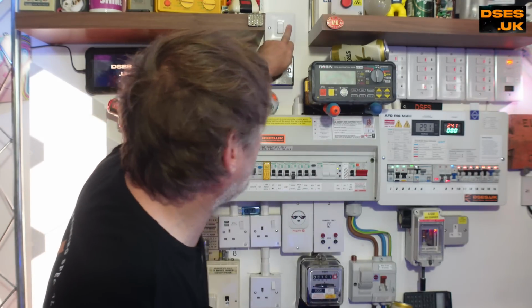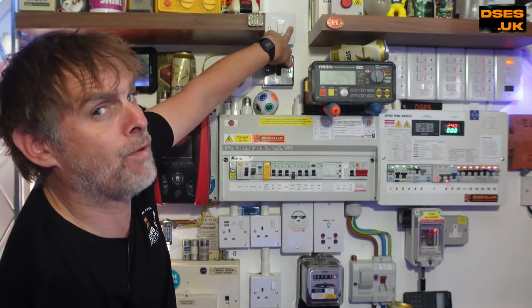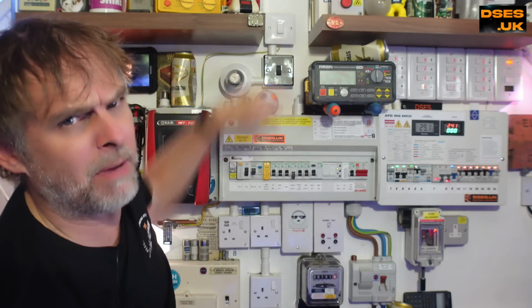In the same way, as already shown, I can give my 115 volts two fingers here and feel nothing. It might have shouted about being a 3-digit number on my multimeter, but this voltage can't drive any kind of load, which is why it's sometimes referred to as a floating or phantom voltage.